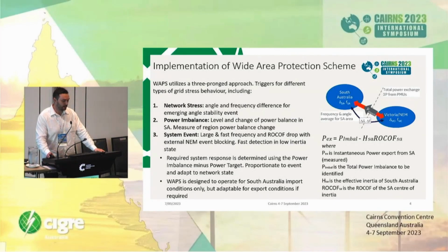And then there's a system event. So this is for more severe events, such as large and fast frequency changes and rate of change of frequency (RoCoF) drops. The scheme itself is bidirectional, so it can work irrespective of whether South Australia is importing or exporting. But for now, it's only active when South Australia is importing power from Victoria.